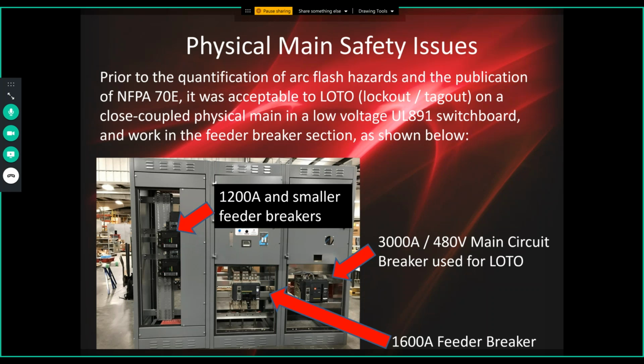And you can see the feeder breakers. So in the old days, we didn't know anything about arc flash. We would lock out that main breaker and we would go to work in that feeder breaker section. And provided we had verified absence of voltage phase to phase and phase to ground and tested the tester before and after the test, we would assume we're safe. And we are safe at that point from shock hazard. But what we didn't know back in those days is that we were not safe from arc flash hazard.